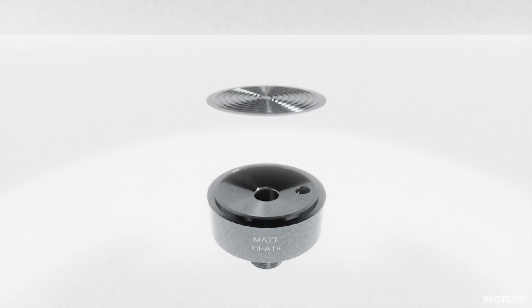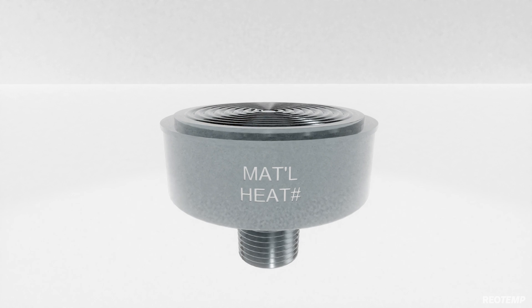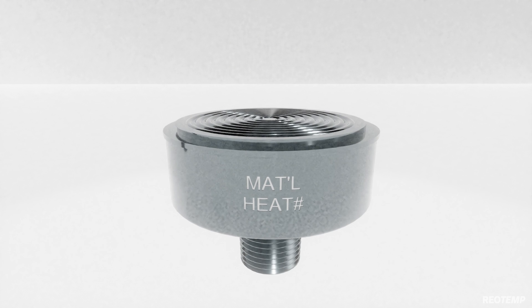The diaphragm foil and lower housing are welded together and helium leak checked. These are the only two items wetted to process fluid and are available in Monel 400, Hastelloy C276, Inconel 625, and other exotic alloys.